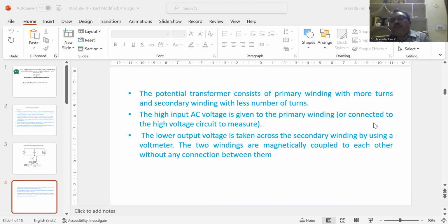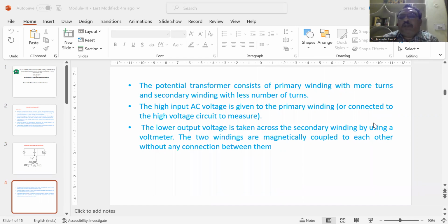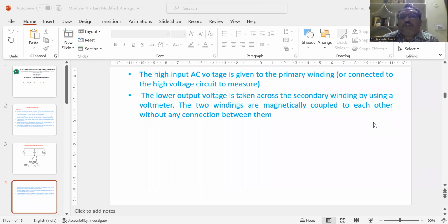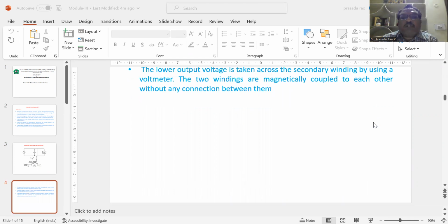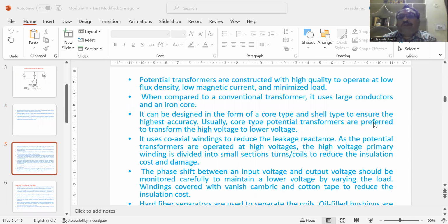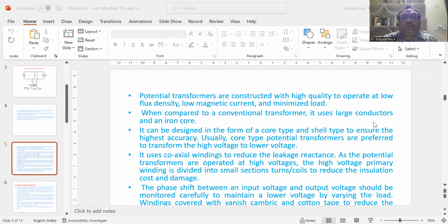The potential transformer consists of the primary winding with more number of turns and the secondary winding with fewer turns. As a result, it works as a step-down transformer. The AC input voltage in kilovolts is applied across the primary, and the reduced or step-down voltage is measured by using the voltmeter across the secondary winding. The primary and secondary of the potential transformer are magnetically coupled to each other without any connection between them. The potential transformers are constructed with high quality to operate at low flux density, low magnetizing current, and minimized load. When compared to a conventional transformer, it uses a large number of conductors and an iron core.